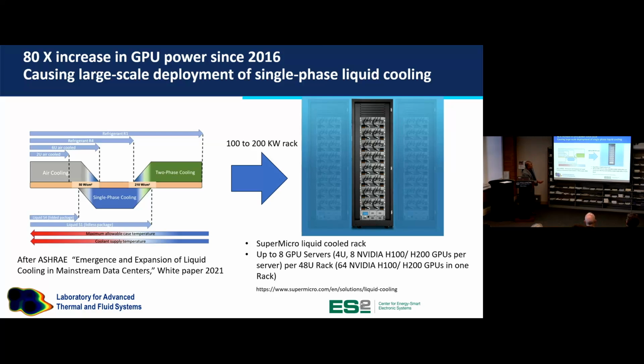So this is an example of a Super Micro water-cooled cabinet where all of these individual servers are high power, high performance NVIDIA GPU servers. The amount of power they dissipate is phenomenal. We used to talk about 20 kilowatts in a rack like this as being a hot rack when cooling with air. Now we're talking about 200 kilowatt racks in my lab at Villanova. That's a humongous toaster oven, right? It couldn't possibly be cooled with air. It has to be cooled with liquid.